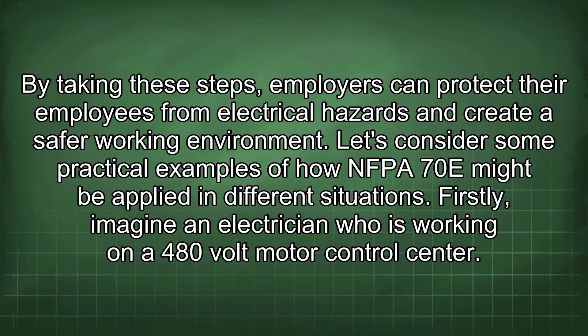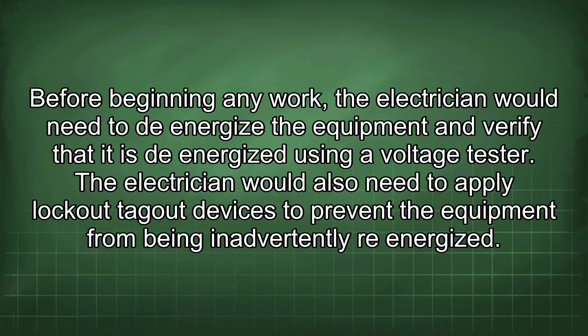Firstly, imagine an electrician who is working on a 480-volt motor control center. Before beginning any work, the electrician would need to de-energize the equipment and verify that it is de-energized using a voltage tester. The electrician would also need to apply lockout-tagout devices to prevent the equipment from being inadvertently re-energized. Once the equipment is de-energized, the electrician would need to wear appropriate PPE such as arc-rated clothing, insulated gloves, and a face shield.